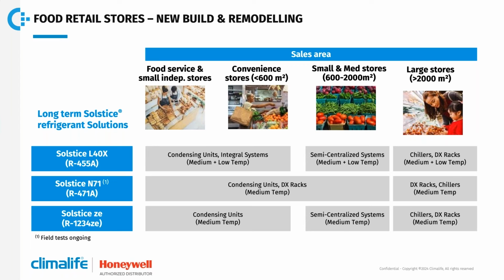In total agreement with what has just been presented here, this table summarizes the potential solutions with a segmentation according to the surface of the store, from the very small ones, meaning food services and small independent stores, to hypermarkets having more than 2,000 square meters, but also for convenience stores and for supermarkets. As you can see here, we have 3 refrigerants having low GWP, less than 150, and ultra low GWP like 1234ZE here, and they are able to propose a solution for all sizes of area.